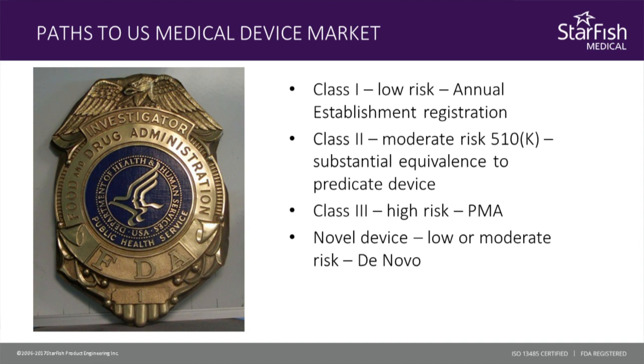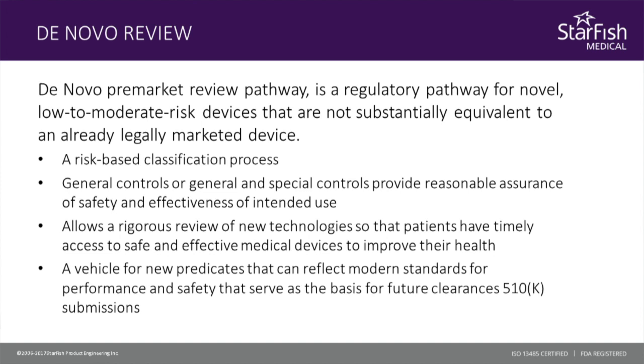And I think that was the idea for Zephyr as well, that it would be the 510K route. And then you have class 3 devices, which are high-risk devices, and you have to go through premarket approval. Those are the devices that are really dangerous. They can kill you or injure you, and for these you have a much longer path, with a lot of clinical work involved, much more requirements, premarket approval, inspection of the manufacturing facility, et cetera. Then the FDA realized that when there is no predicate and the device is not class 1, the regulations were automatically putting those not substantially equivalent devices in class 3. So they came up with an easier pathway, and that's how the de novo was born, as a low to moderate risk pathway for devices that do not have predicates.